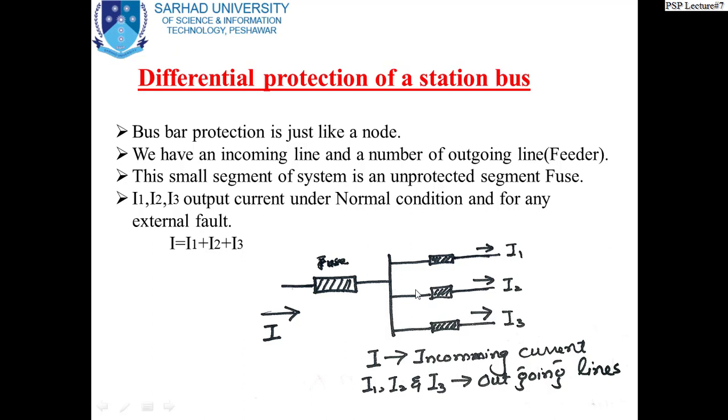So this bus area is a totally unprotected area, because this relay's protection region is somewhere here, this one somewhere here, and the third one somewhere here, and this one we will see over here. They cannot see, in most cases, beyond their position. Therefore this particular bus area is a totally unprotected area. You see, from the basics of protection, you cannot leave anything unwatched.